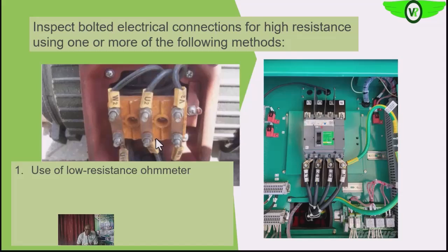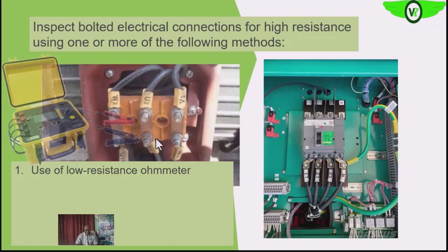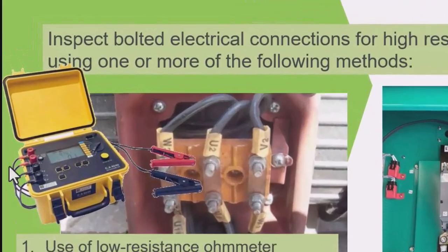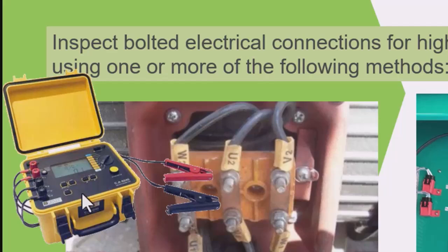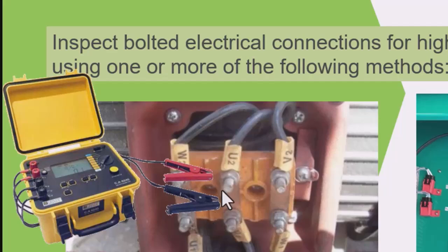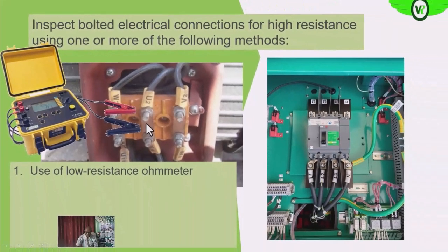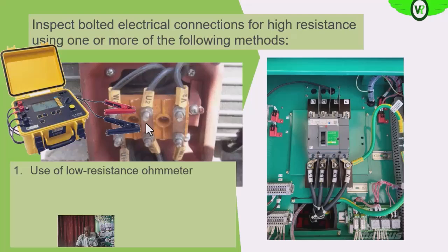So if it is beyond what is expected, of course, we need to either tighten up, or loosen, clean, and then tighten up that particular connection. So this is an example of the low resistance meter that we can use to test the connections. We'll set it to the micro-ohm or milliohm range, and then test the resistance at those terminals to see that high resistances are not building up.